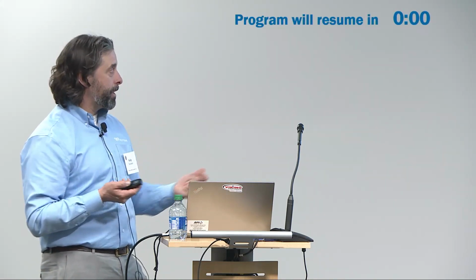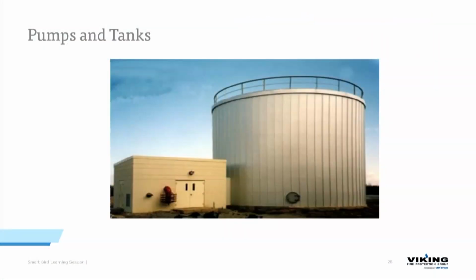Good example of a water tank in a fire pump room. My assumption on this one is that it just feeds a distribution loop around a facility. Again, this looks like an insulated, heated tank. The funny story about that is I went rounds with a guy from Texas saying, well, I'm in Texas, I don't have to do that. But his ambient temperature, if you looked at his city, or the temperature that it can get down to, was 40. So it didn't matter. The code states that he needed to heat it, and he was going to go back to his fire marshal and get back to me. So I haven't gotten a call yet.